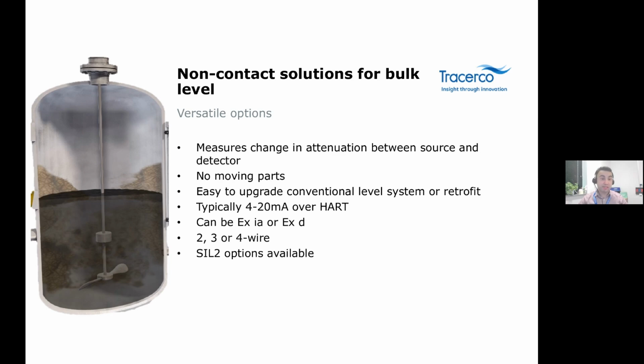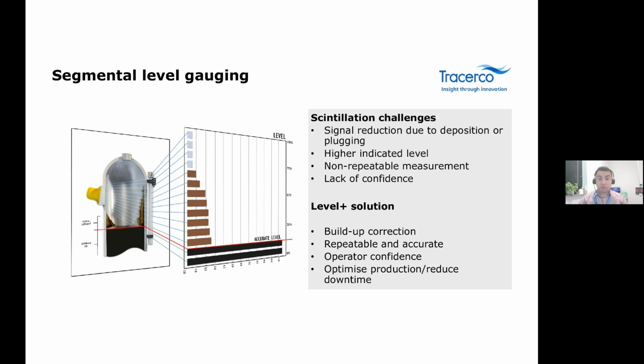Some of them are Ex ia, some are Ex d, with multiple wiring options available and various safety integrity levels, such as SIL2. Some standard application equipment uses scintillating technology, which would see a reading reduction when there is buildup or foam present. This would read a higher level than what is actually inside the vessel. This measurement would not be repeatable and can lead to a lack of confidence in the level system.